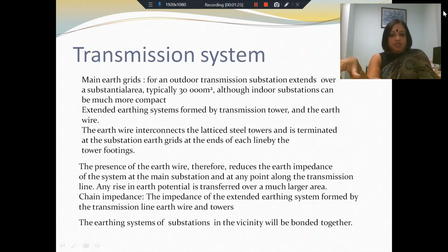At the end of the transmission tower, you also have the tower footing resistance, which can be manipulated. So therefore, the earth impedance of the system at the main substation and at any point along the transmission line is reduced. The earth impedance is therefore reduced because it is an extended system. It's not one single conductor going to ground. It is an extended system. There are grids. There is an earth grid, and then you have the earth wire, you have the transmission tower. When you look at this entire interconnected structure, the total earth impedance from any point on the system to ground is pretty low. As a result, here what we are trying to do is reduce R.